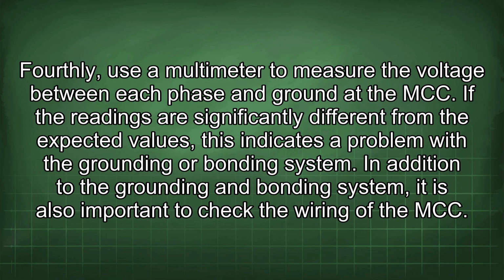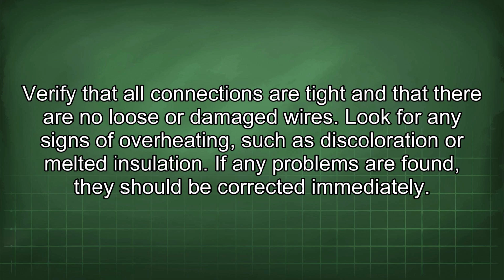In addition to the grounding and bonding system, it is also important to check the wiring of the MCC. Verify that all connections are tight and that there are no loose or damaged wires. Look for any signs of overheating, such as discoloration or melted insulation. If any problems are found, they should be corrected immediately.